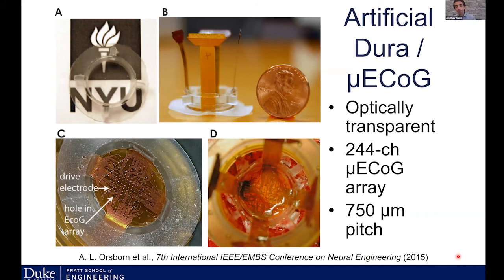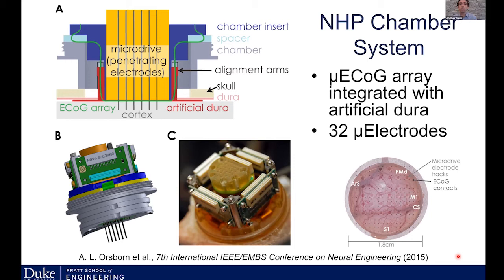We mold our micro-ECoG arrays into an artificial dura made out of silicone, which is optically transparent and allows us to implant our electrodes through a cranial window system with our collaborator Bijan Pesaran. This allows us to test new electrodes in an animal implant without sacrificing an animal for every device we want to test. We can replace electrodes through this artificial dura in a matter of a day, maintain optical access to see the brain underneath transparent arrays, and we incorporated mounting hardware for a micro-drive of penetrating electrodes that can record simultaneously from in the cortex as well as from hundreds of surface electrodes.